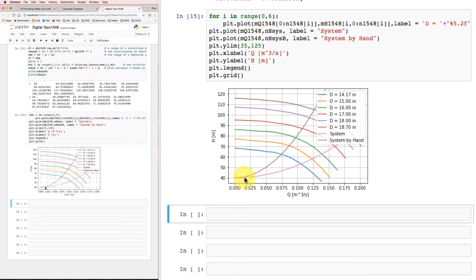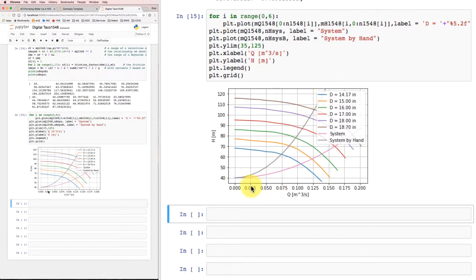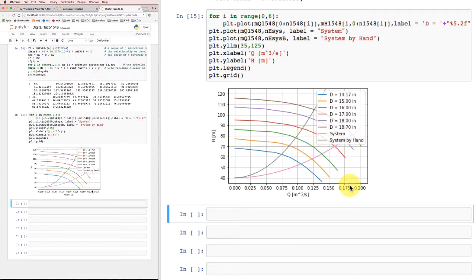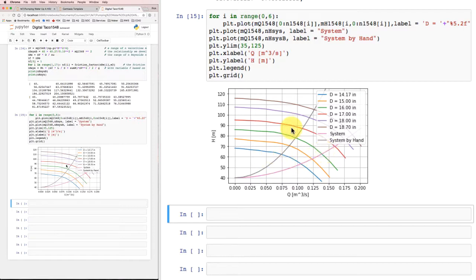So here's the line that I had before, that was my original system with my 6-inch pipe. When I switched up to an 8-inch pipe, I have much lower losses and the result is that the flow for this 8-inch pipe for the same loss or the same head rise across a pump of about 80 is more like 0.185 rather than 0.1. So I'm seeing much lower head requirements to get the same flow or much higher flow for the same head delivered by the pump.